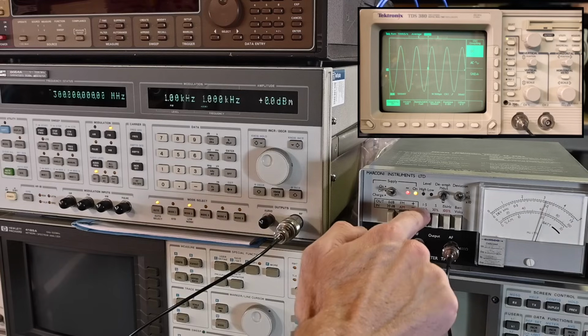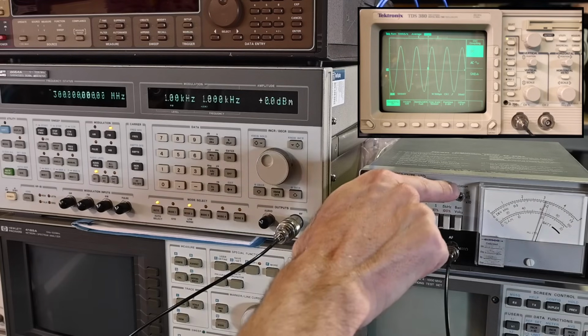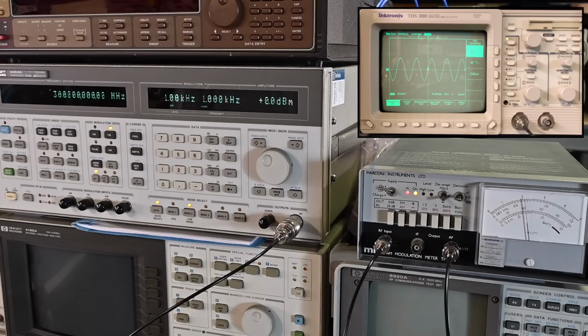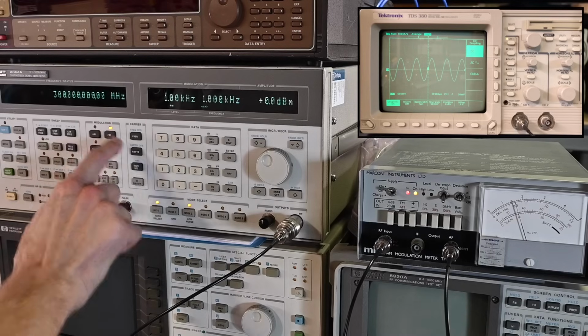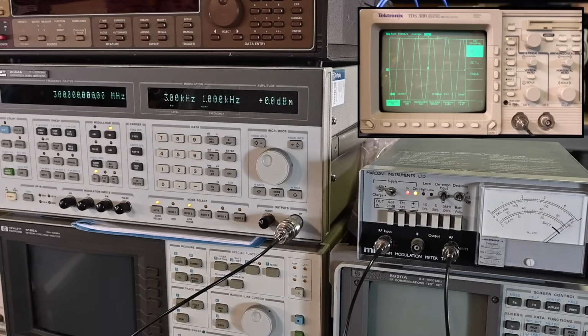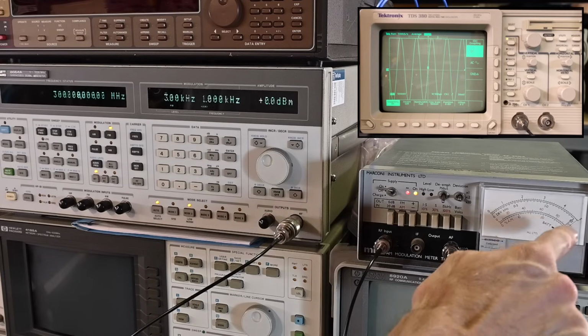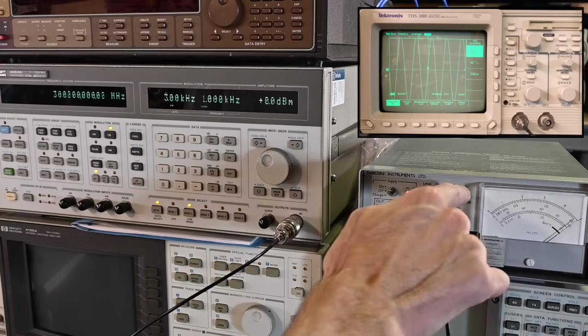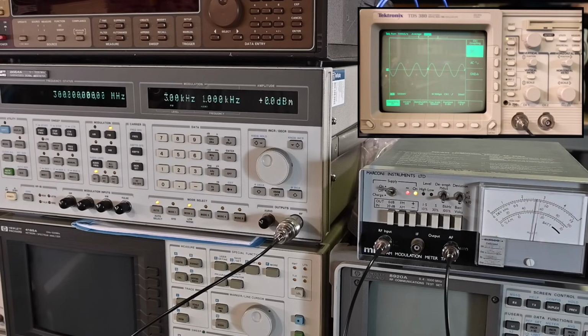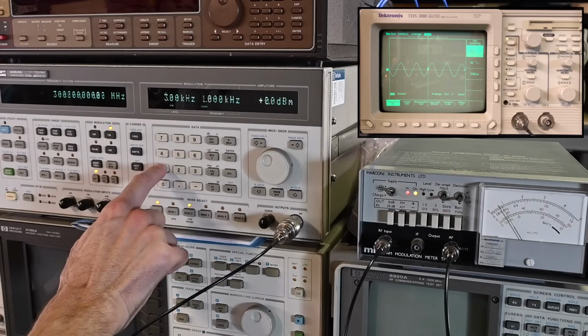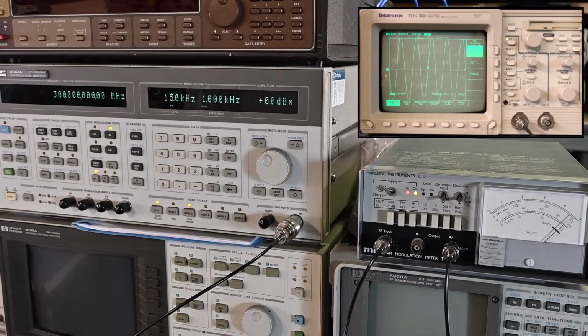Leaving this on 1.5 kilohertz, if I change this deviation range switch to 2, so 1.5 times 2 is 3, if I go to FM 3 kilohertz, it should go to full scale, and yes it does. Perfect. That's working the way that it's supposed to. We're reading on the 1.5 scale, but we're multiplying it by 2. And then if I go to times 10, of course 1.5 times 10 is 15. So if I go to FM 15 kilohertz, it should go to full scale, and yes it does. So perfect, no issues whatsoever on that range.